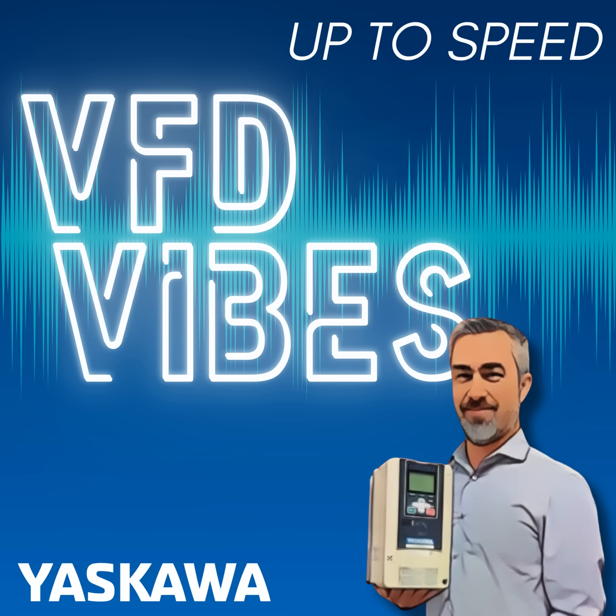Active harmonic filters can have performance at or under 5% THDI and can be applied at a single point in an electrical network. That simplicity is nice. Often if you're dealing with a situation where a customer has an existing installation and needs to fix a harmonics problem, it can provide an easier solution. One point of harmonics mitigation, however, means that if that active filter faults or fails, you could see a large surge in unwanted harmonic content in your network and thus have problems.